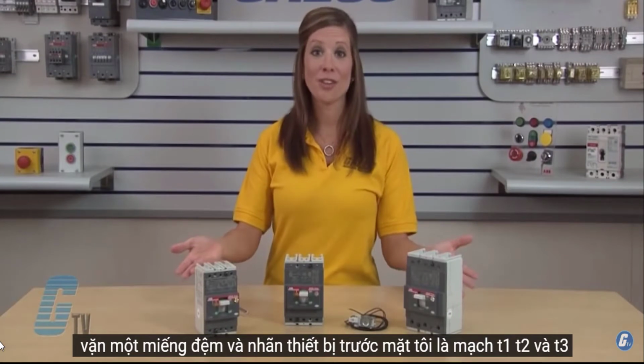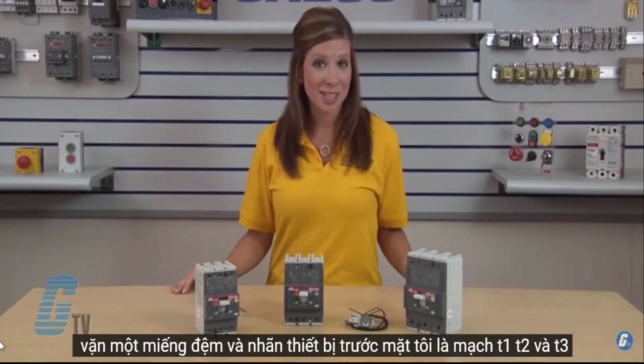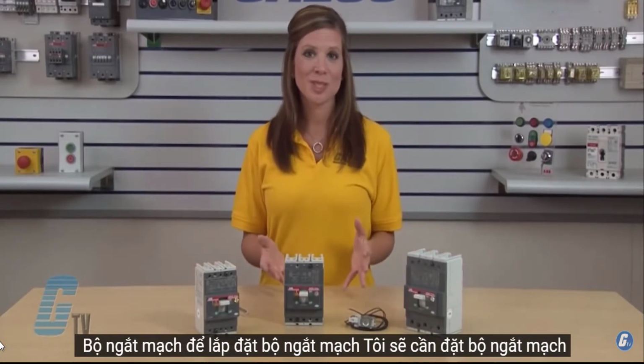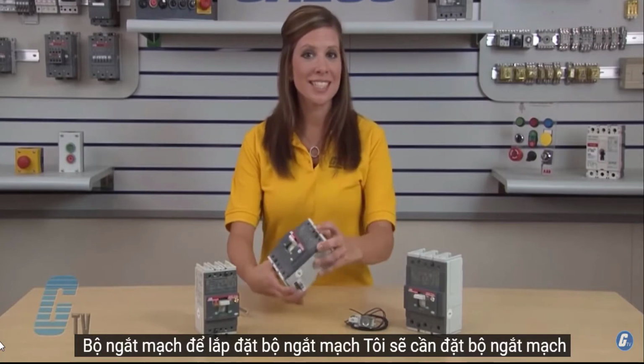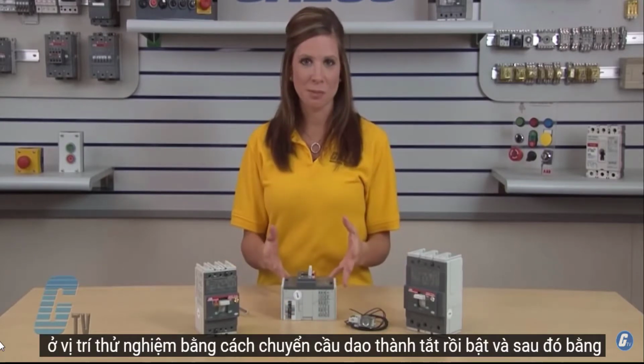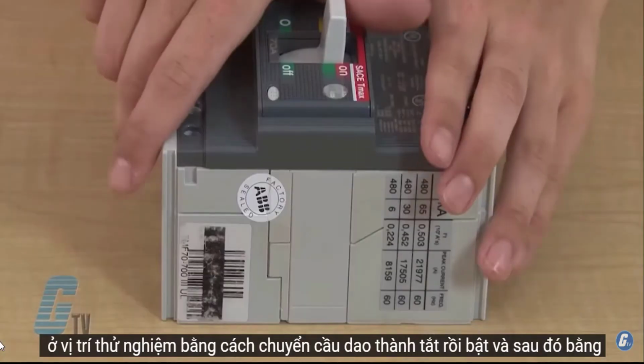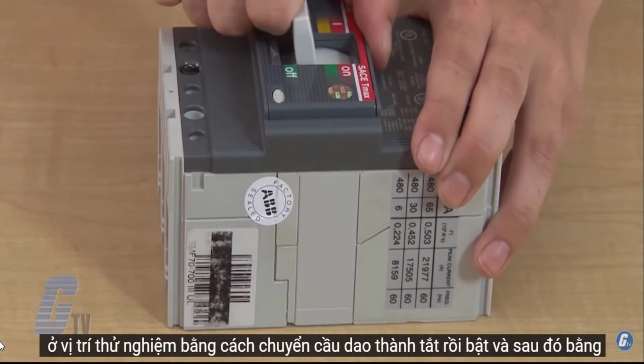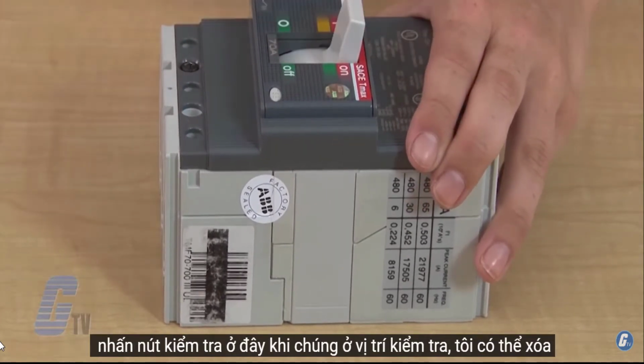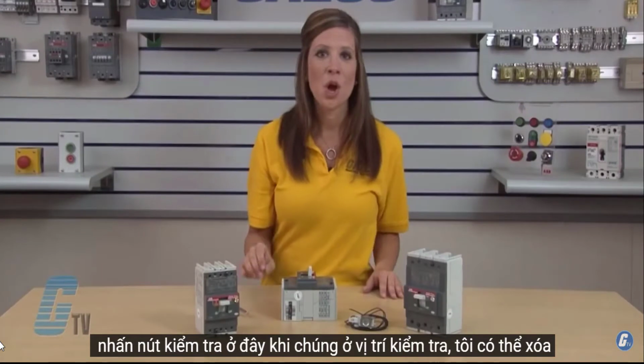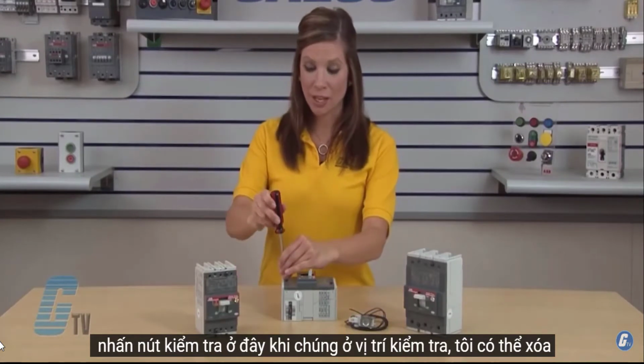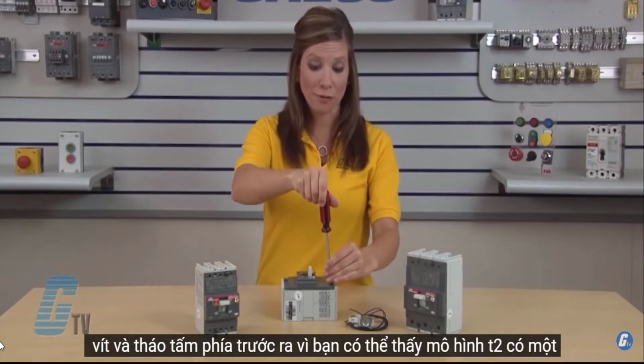In front of me are the T1, T2, and T3 circuit breakers. To install the shunt trip unit, I will need to set the circuit breakers in the test position by switching the breaker to off, and then on, and then by pushing the test button here. Once they are in test position, I can remove the screws and take off the front plate.